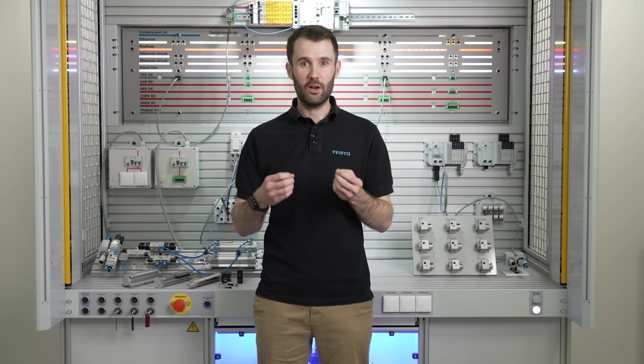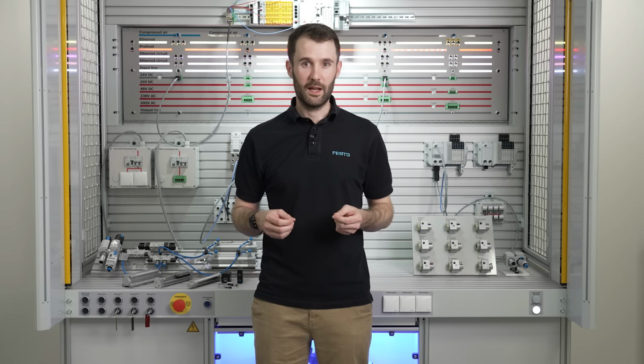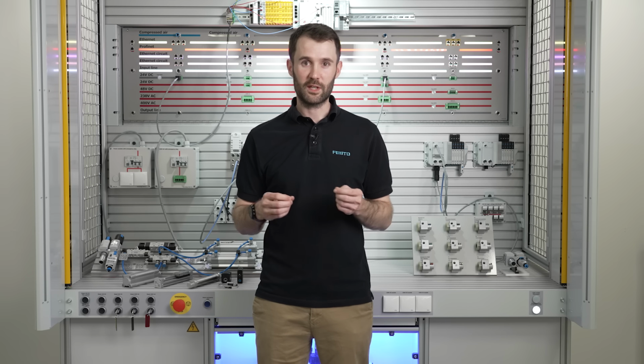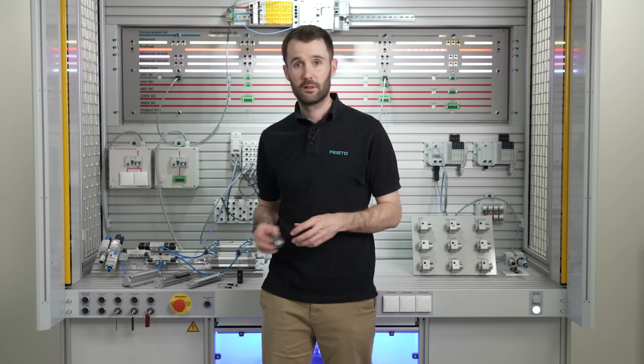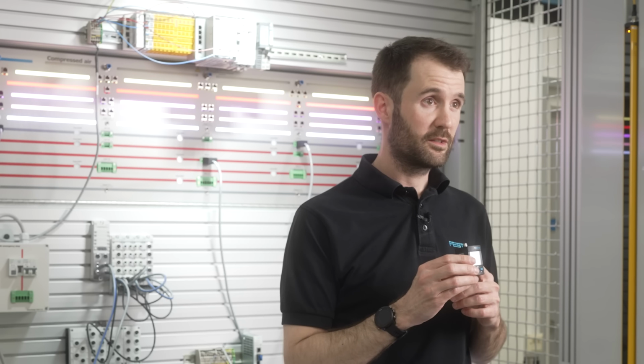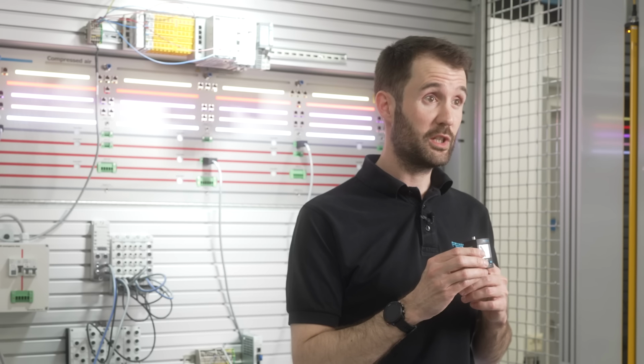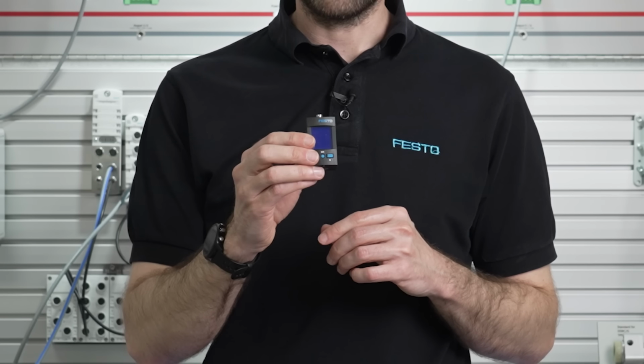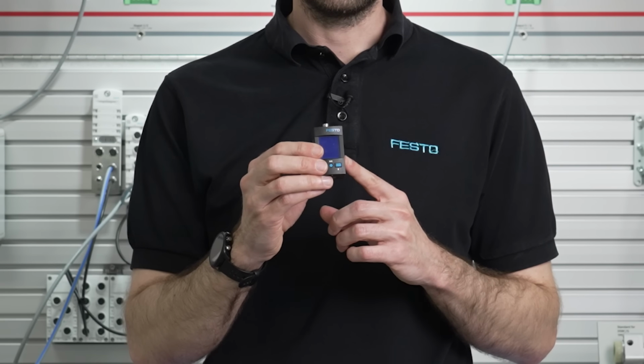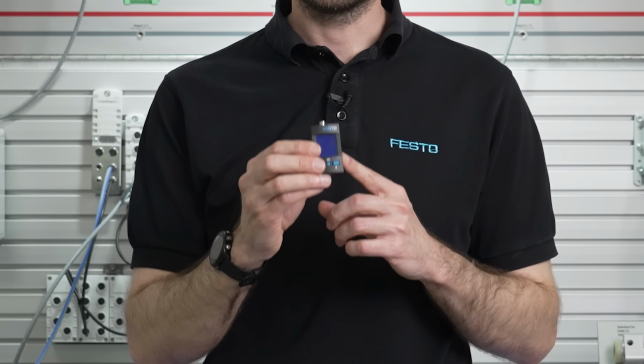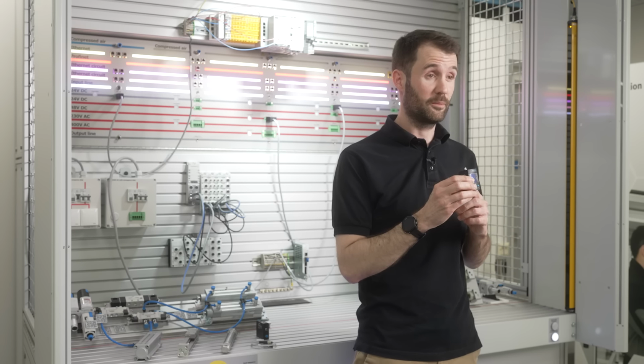So finally, predictive maintenance. And for predictive maintenance, we want to try to predict early failures as soon as possible. And to do this, we use a wide array of sensors across the machine to get data back to make decisions quickly and efficiently. So let me just go through a couple of these. We may utilise a pressure sensor to detect the integrity of the pressure to the main line of the machine, or maybe at the subcomponents, as we said, a pneumatic cylinder earlier, to make sure the right pressure is getting to the platform, or even look at trends like pressure loss.